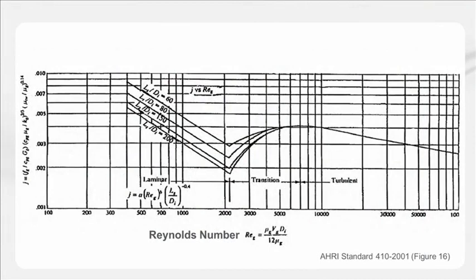Fluid velocity is also important because it is one of the key factors for determining flow turbulence, along with fluid density and viscosity and tube diameter. As the turbulence of a moving fluid increases, so does its ability to transfer heat from the tube wall to the fluid. The AHRI 410 chart depicts fluid turbulence as described by the Reynolds number on the x-axis, which is the primary driver of the heat transfer coefficient on the y-axis. The chart plots the Colburn J heat transfer factor versus the Reynolds number, used by coil manufacturers to rate their selection programs.